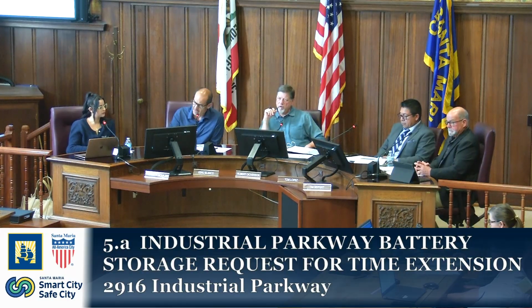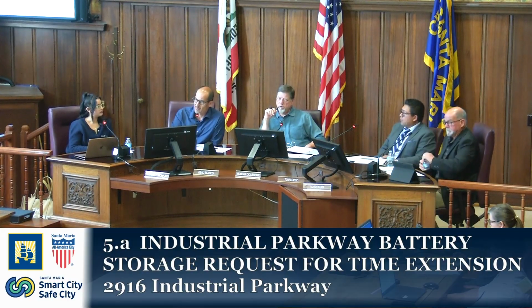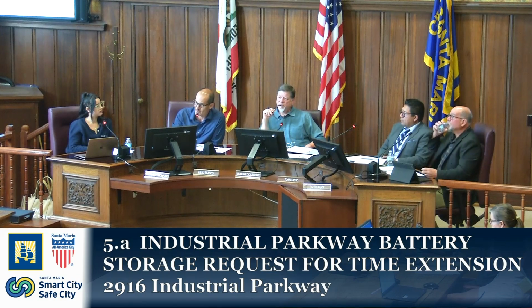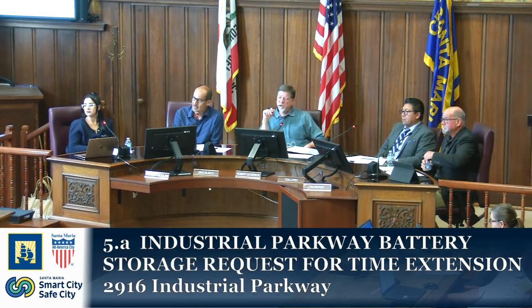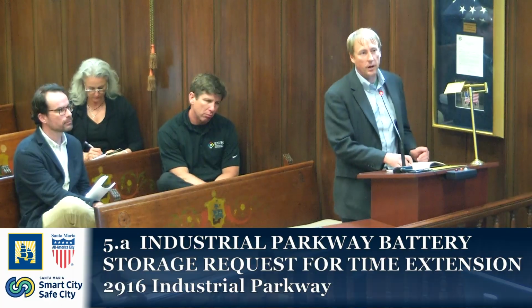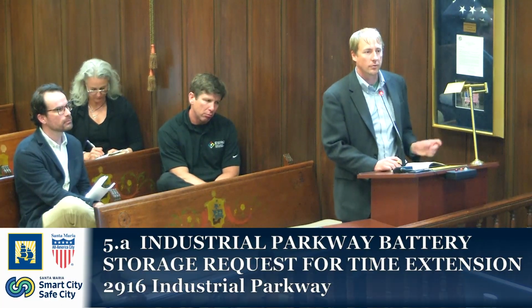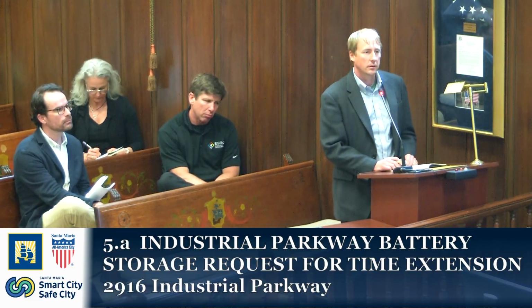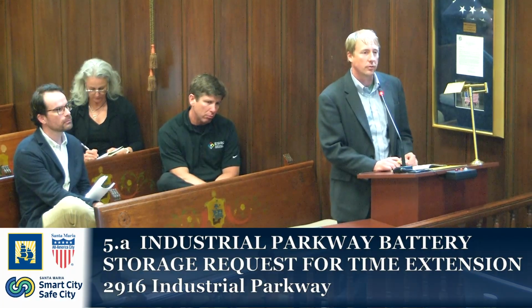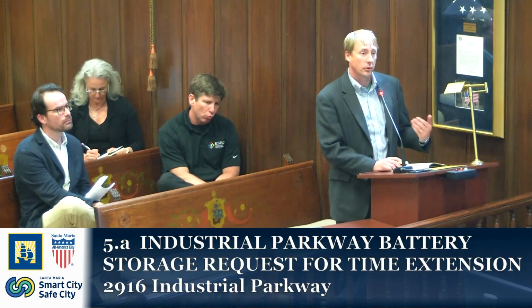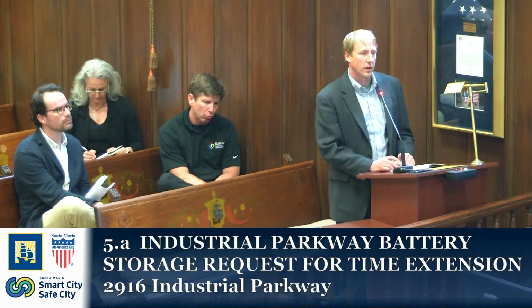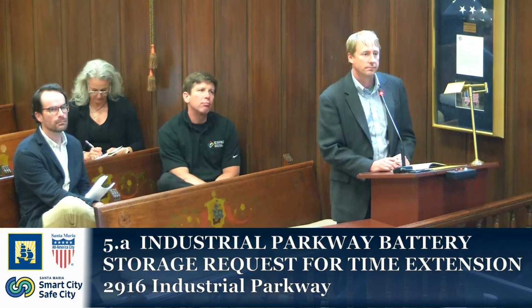Just curious, what kind of temperatures, normal operating temperatures, would you see around these cells? What kind of increase in temperature would you expect? The normal operating range is about 60 degrees - I think we go from 30 to 90 Fahrenheit, but that's what the design is for. And the battery has a liquid cooling system because it does generate a little bit of heat when it operates, to dissipate that heat. Okay, thank you.